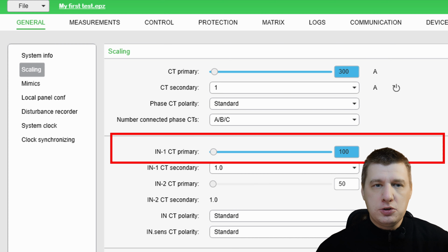CT primary monitors your load and detects short circuits between phases. In1 CT primary monitors the spill current to detect earth leakage or ground faults. Secondly, they connect to different terminals. Phase CTs go to terminals A9 through A12, while the In1 earth-fault CTs connect to A13 and A14. These settings are independent. You can have 1000 amps CT primary for your heavy load, but 20 amps In1 CT primary for extremely sensitive ground fault detection.